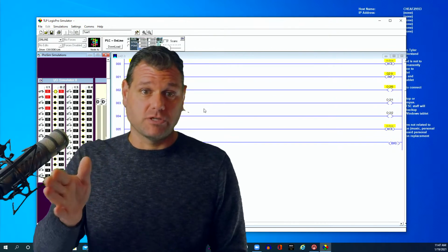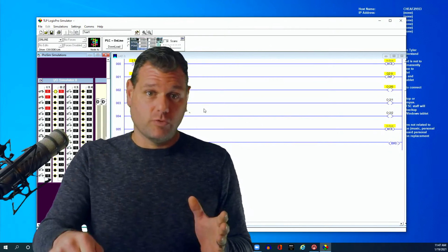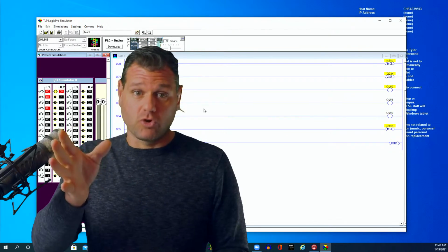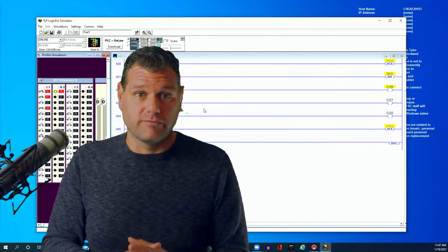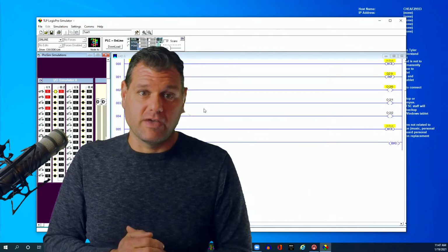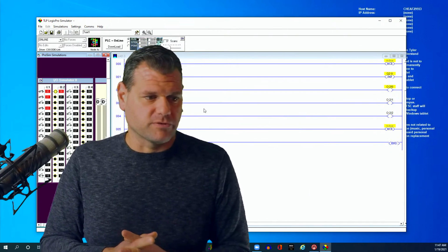So right here, when the MCR goes off, that jump is dead as well. So you never jump into a MCR, and you try not to put it inside. This would work because it would never jump to or from anything because it's in the fence. But yes, an MCR does not affect anything outside of that fence. Does that kind of explain what you're saying?